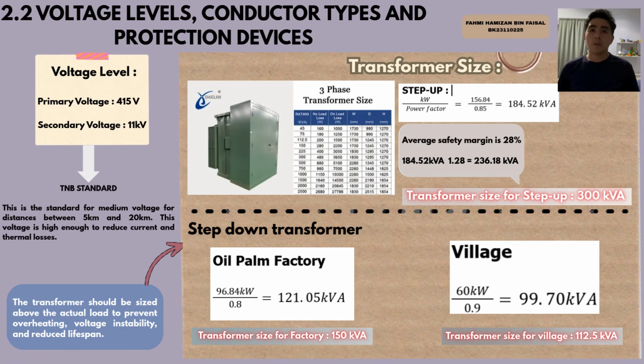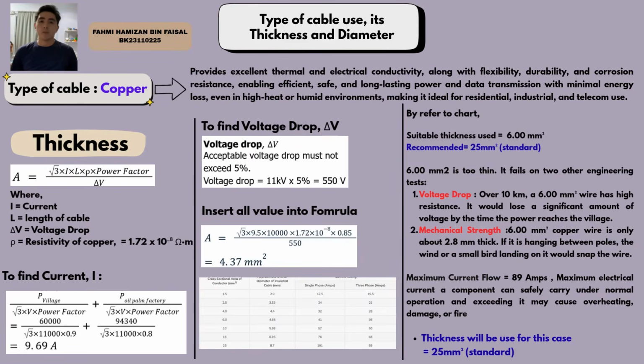This medium voltage level is suitable for distance between 5 to 20 kilometers. After applying a 28% safety margin, a 300 kilovolt ampere step-up transformer is selected. For a step-down transformer, 150 kilovolt ampere is used for the oil palm factory and 112.5 kilovolt ampere for the village. Copper cables are used due to their high conductivity, durability, and corrosion resistance.